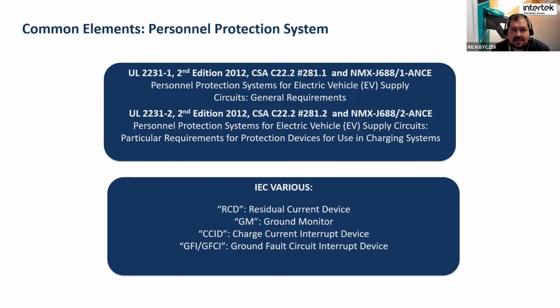To alleviate this, the CCID circuit standards allow for different calculations for that time constant, to allow for maybe a higher current level to pass through an alternate ground path, but the trip time is reduced so that you have the same level of risk mitigation and safety in terms of preventing electric shock to someone if that ground path was essentially through a person.